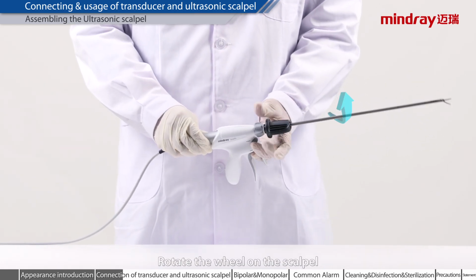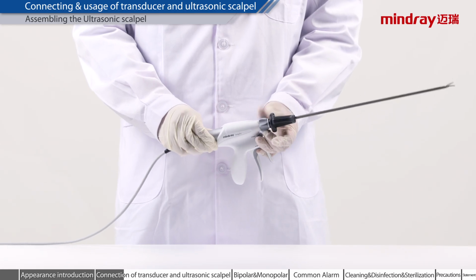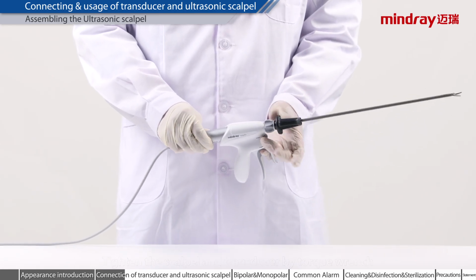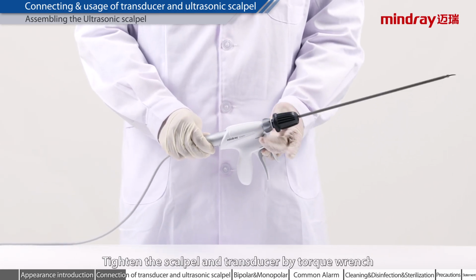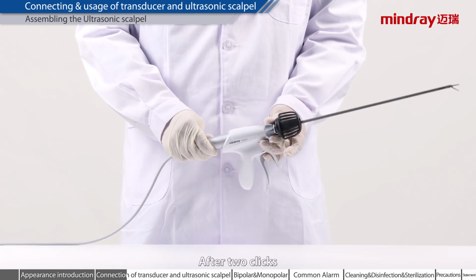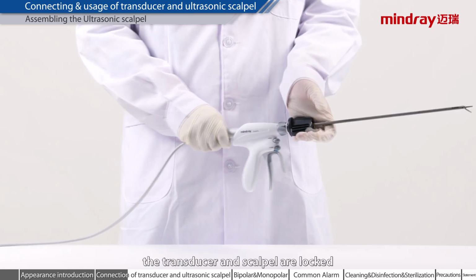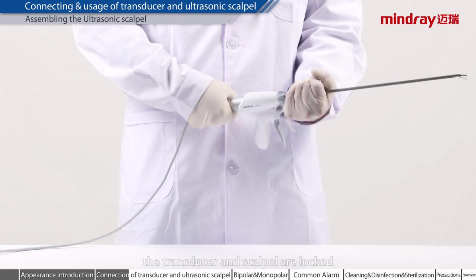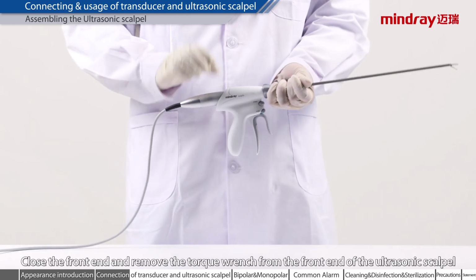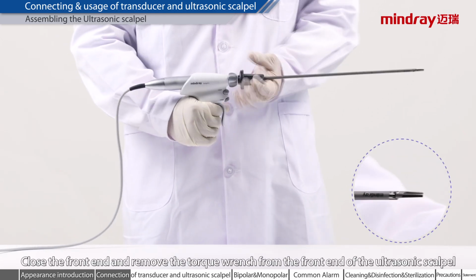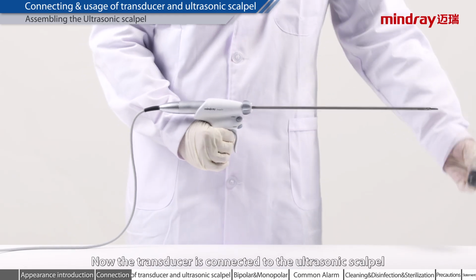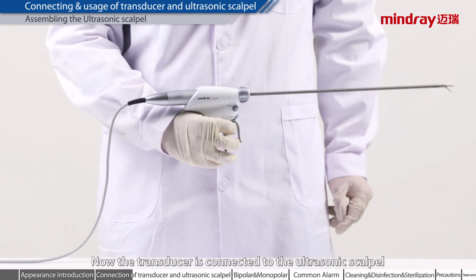Rotate the wheel on the scalpel. Tighten the scalpel and transducer with the torque wrench. After 2 clicks, the transducer and scalpel are locked. Close the front end and remove the torque wrench from the front end of the ultrasonic scalpel. Now the transducer is connected to the ultrasonic scalpel.